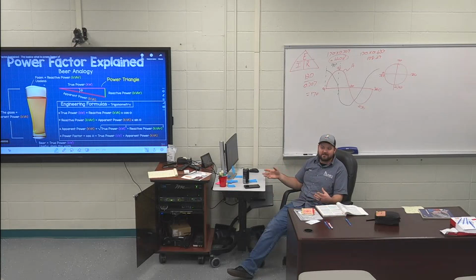Plants use a lot of induction motors, right? Motors are on everything: hoists, lifts, fans, blowers, pumps, everything's got inductive motors on it. So you have a lot of inductive loads, which means a lot of reactive power. To compensate, you can put in big banks of capacitors, and capacitors offset your inductive loads, so you don't have to pay that penalty. That's as far as I'm going to take this with power factor, but power factor is pretty much just how well you are using your power, or how well your power is provided to you.